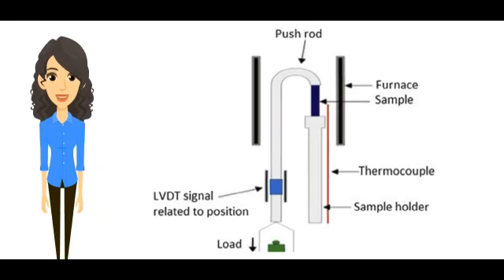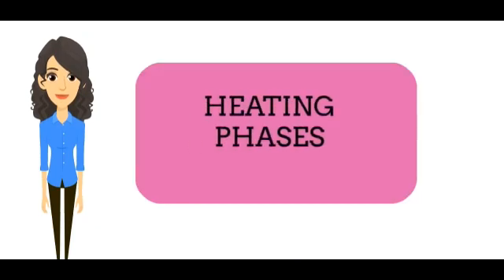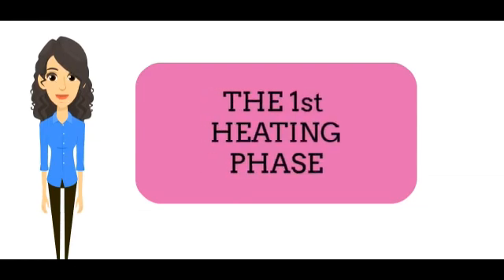A small load acts on a specimen and the expansion of the specimen is measured. There are two heating phases in TMA. It yields information about the actual state of the specimen, including its thermal and mechanical history.